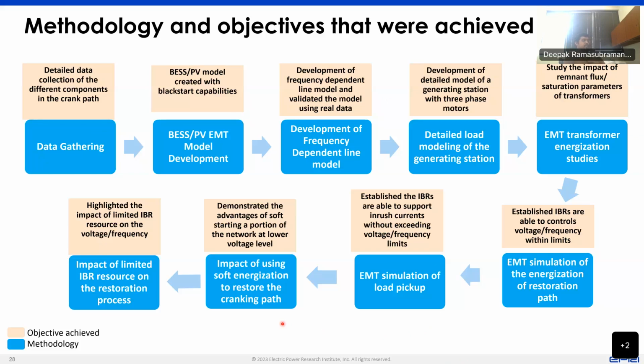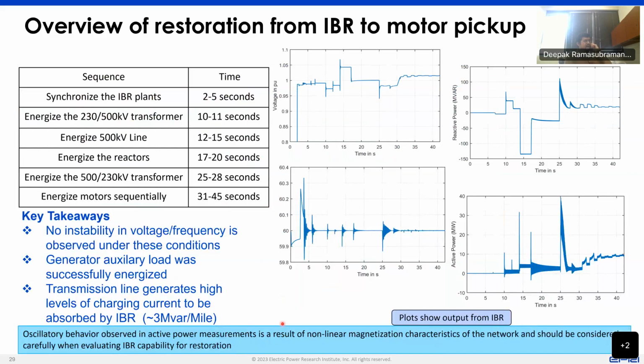Because there might be a need to soft start. There might be a need to have a soft energization. There could be some other perspective with respect to what voltage levels should we meet, what kind of frequency band can we tolerate, and so on. And then would that change if you have a limited capability of the resource that is available? So a very high level view of the results looks at how, if we do have this variety of factors that are considered, then you can actually make the inverter-based resource successfully energize and black start the entire path.